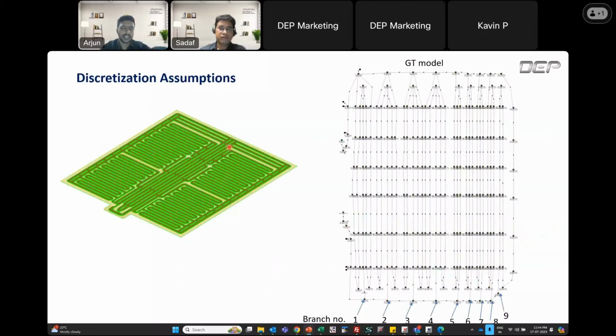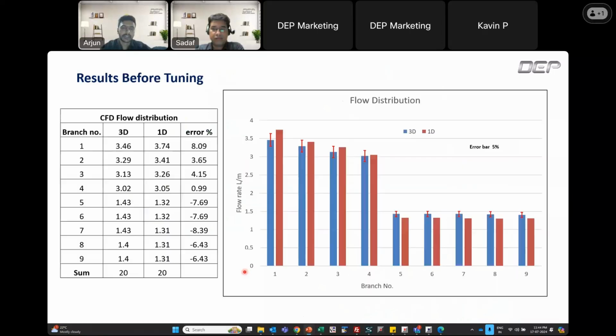Once you do that extraction and get the fluid core and convert it into a GT suite model, as you can see on the right, this is the GT suite model. We are mainly concentrating on the flow distribution on these branches 1, 2, 3, 4, 5, 6, 7, 8, as you see at the bottom. Once the cooling flow of 20 LPM is flowing through this, we need to monitor how much flow is going through each branch, that means each module. After running this analysis, we'll get results like this: how much flow is going to the first branch, second branch, until 9, and this is the error percentage.